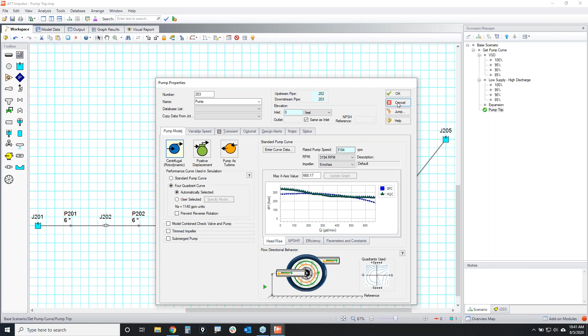So that's one of the key new features on pumps: we have streamlined the calculation for total rotating inertia to take out the guesswork that you'd have to put in, and we also calculate a 4-quadrant curve for you. But again, those are some very complicated parameters, and it's very important for you to understand where those numbers come from. So be sure to read the documentation on that.